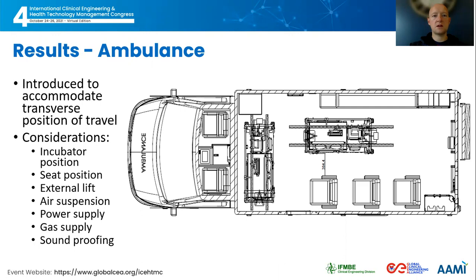Some other considerations we made when designing the ambulance included the position of the incubator and the position of seats, which must be configured so that there is ease of access to and visibility of the patients. The external lift had to be sufficient to accommodate greater than 165 kilograms in weight. In addition to the hydraulic operating mechanism, the lift must be operable manually in case of emergency or hydraulic failure, and had to include side safety rails to prevent the incubator from overshooting the ramp. The chassis needed to be fitted with air suspension to reduce the occurrence of travel sickness in staff. And in addition to the battery backup on the equipment itself, the ambulance also included two alternative independent power sources, a 220 volt AC supply from the ambulance inverter and a 12 volt DC supply.